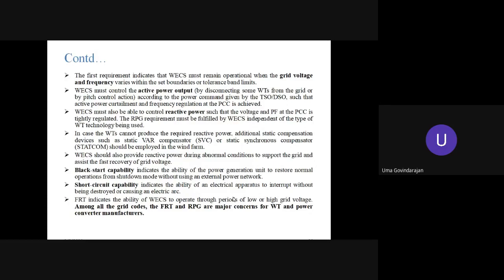The third point is that wind energy conversion systems must also be able to control the reactive power such that the voltage and the power factor at the point of common coupling are tightly regulated. That's very important. The voltage profile at the point of interface between the generation and the utility, between the active load and the utility, can be improved by supplying reactive power. We can also make the WECS have active control of the reactive power at the interface between the wind generator and the grid. Therefore, if reactive power control is exercised at the interface, then it is possible to do voltage control of the grid and also frequency control.